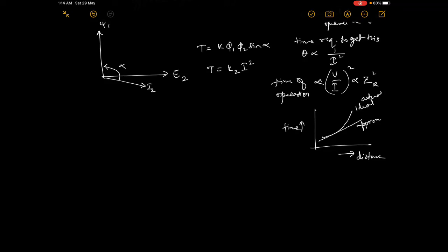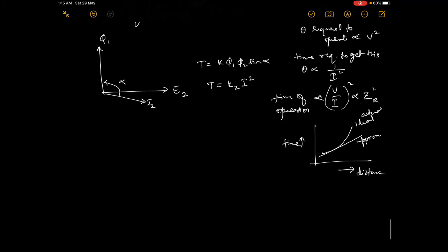So this distance relay actually is a combination of an overcurrent element and the voltage restraint element. The overcurrent element consists of a primary winding connected to the CT. I have not shown the diagram here, but hope you remember it. It is induction type, connected to the CT through plug setting, and the secondary winding is connected in series with the lower magnet. EMF was generated due to this transformer action, and also eddy current was produced. Hence your torque was proportional to I square.